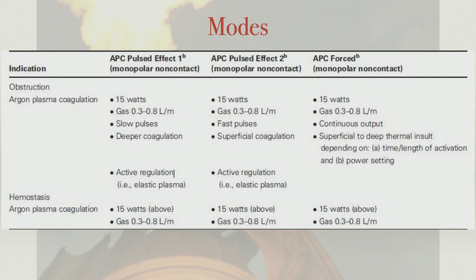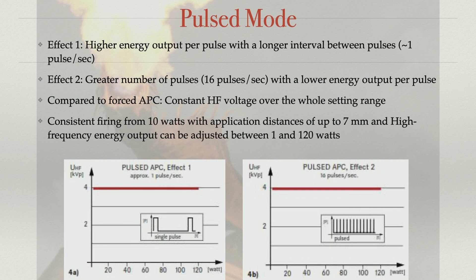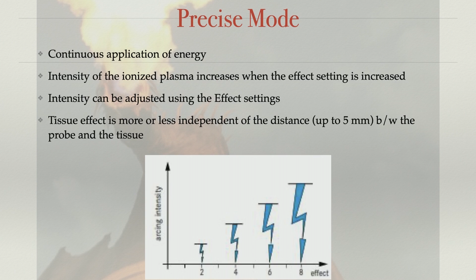In pulsed mode, as you can see in the graph, there are multiple pulses of electrical activity that the generator gives off, and that's what causes the kind of effect, and therefore it's not a sustained response that you're giving for the electrical current. And for the precise mode, the intensity of the ionized plasma increases as the effect setting is increased. So that's basically what the precise mode is all about.